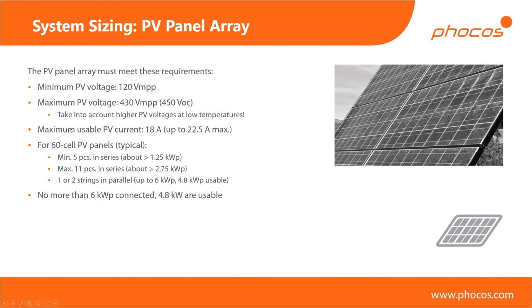So typically, this is the correct order in how I would size such a system. I would always look at the minimum PV voltage of the inverter. So in this case, we have 120 volts for the 48 volt 5 kilowatt model, and at the maximum PV voltage, which is 430 volts MPP and 450 volts open circuit. And you need to make sure that you never surpass the 450 volts, even if it's cold outside. You might have very cold winters, and you probably know PV modules will output a higher voltage when they're cold, so you need to take that into account for your region.